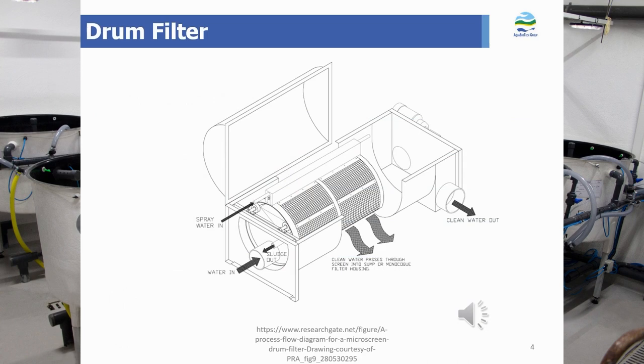One of the main components in mechanical filtration is the drum filter, which is one of the most common equipment for removing solid materials larger than 20 micrometers. Drum filters with mesh smaller than 20 micrometers are also available; however, that compromises the water flow and is not really viable.